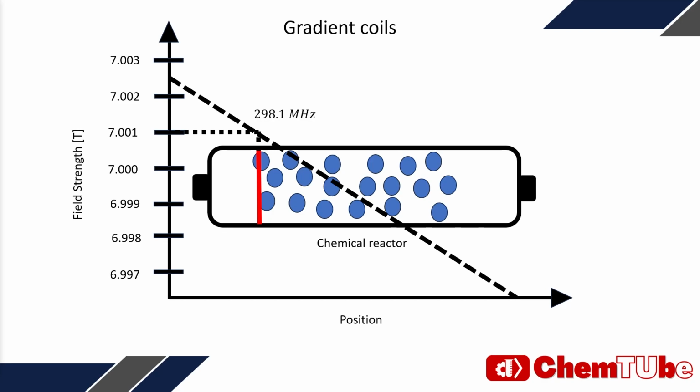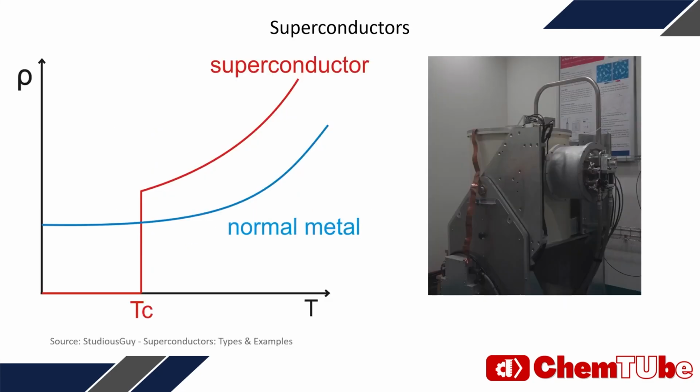The MRI machine at the TUE can produce a field strength of 7 Tesla. The field strength of 7 Tesla can only be achieved using superconducting materials. These materials' resistance reaches zero when temperature is near absolute zero, allowing us to create a very strong electromagnet. Usually, MRIs use liquid helium to cool the superconductor to 4 Kelvin, as the boiling point of liquid helium is around 4.2 Kelvin. This is also why the cost of operating this machine is high, as it has to be constantly kept at this temperature.